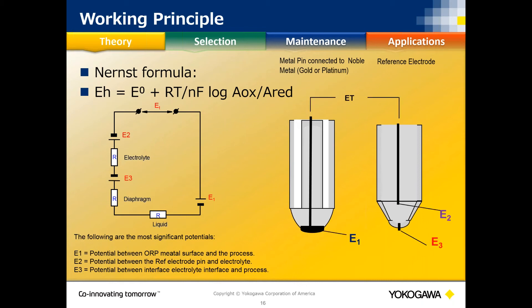The electrical circuit for ORP is less complicated than for pH. We have E2 and E3 — the reference pin on the right-hand side — which gives us zero. If E3's junction is plugged or coated, that changes the equation and gives us erroneous readings. E1 is what we're actually measuring — the millivolt value generated on that platinum pin. A good solution ground is still important, just like with pH.